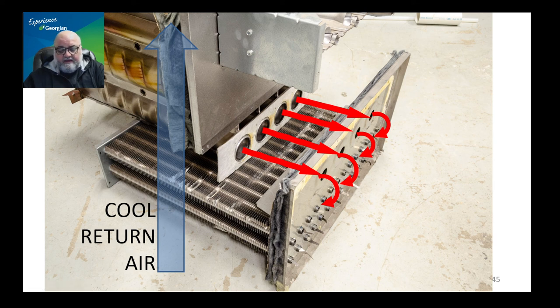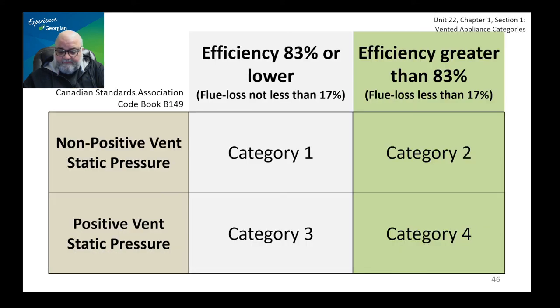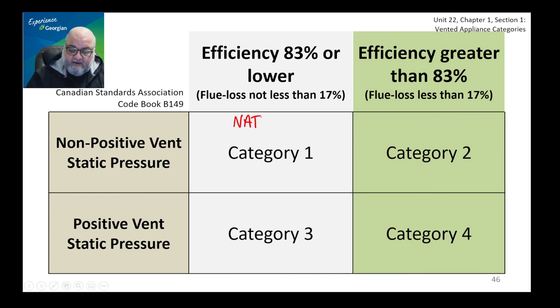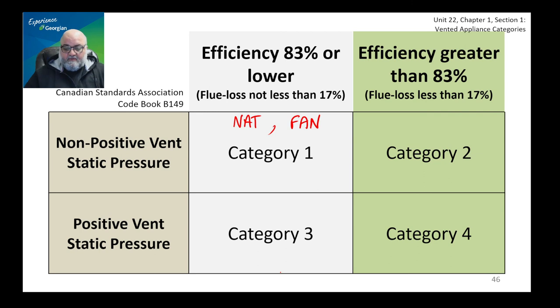The secondary heat exchanger can handle condensation for a very long time. So here is the final look of the visual aid I use: for category one, flue loss is 17% or higher, non-positive static pressure — natural draft or fan-assisted burner. For category two, flue loss less than 17%, non-positive static pressure. Category three has flue loss of 17% or higher with positive static pressure. Category four has flue loss less than 17% with positive static pressure — the high-efficiency condensing category. For the next lecture, we're going to start the basics of vent sizing.